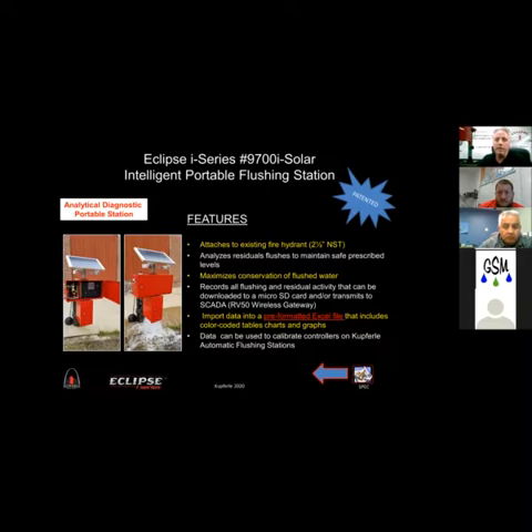Another nice thing about this device too is I leave it in a spot and I capture a number of pieces of information about residuals, turbidity, so on and so forth. And it'll tell me exactly how long the device is flushing to maintain that parameter or residual that I want. So I get the data back and I decide, you know, I need to put an automatic flusher on this dead end because we're having residual issues. I put the automatic on the dead end and I get ready to program the controller. And what I do is I take the data from the data sheets that I got from the machine. They'll tell me exactly, down to the second, how much I need to program the flusher to flush. So I'm very efficient with my automatic flushers based on the data that I get from this device that I can move around my system.